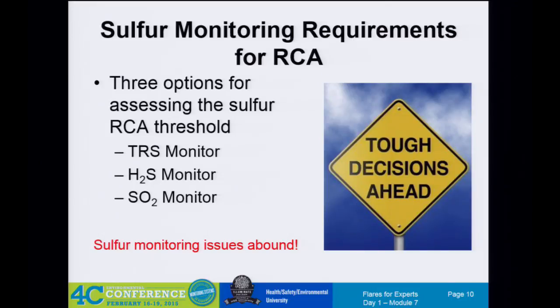They also gave us the option of using the H2S monitor. But again, because they're looking at total sulfur as the number they want, you now have to develop a correlation from your H2S measurement to your total sulfur measurement. That involves a lot of correlation sampling, the 10-day initial event plus once a week. If you get too far out of your measurement range, you're doing another 10-day sampling event. There are facilities that did go down this route, but most people, once they hear how many samples are required, say no. My favorite phrase is we're not good at getting samples, so they basically said we're going to skip that. Then they threw out this SO2 monitor option.